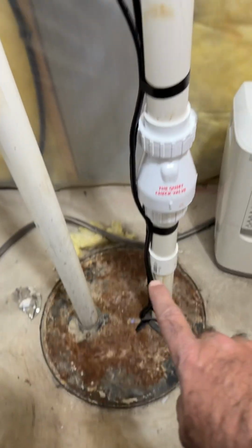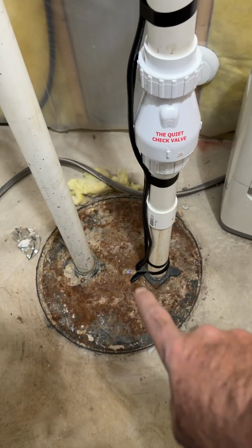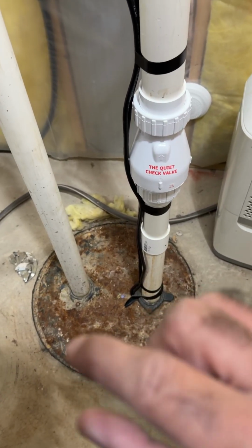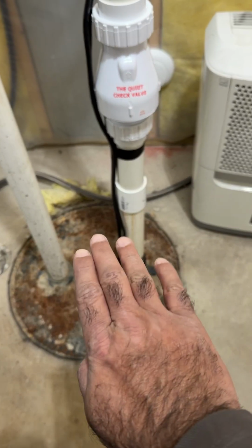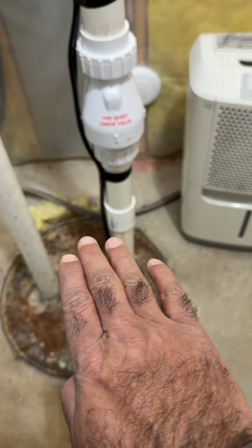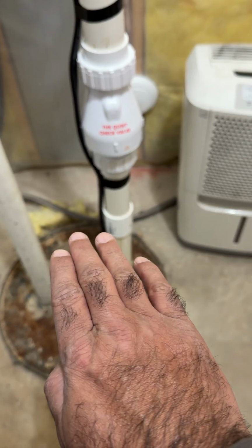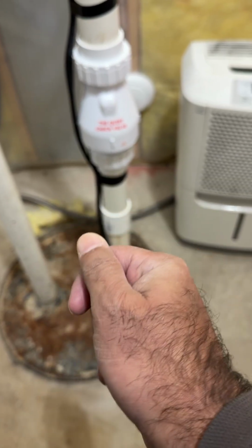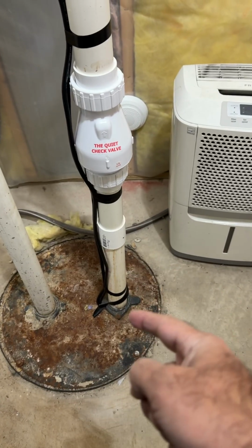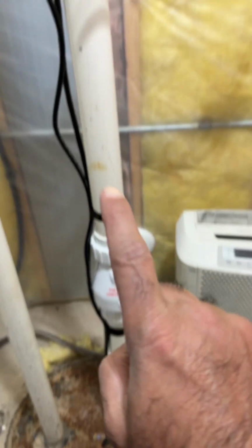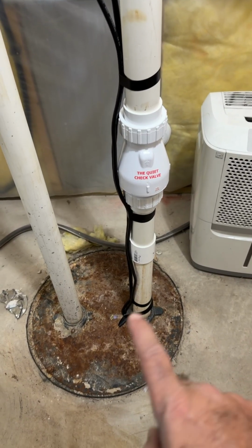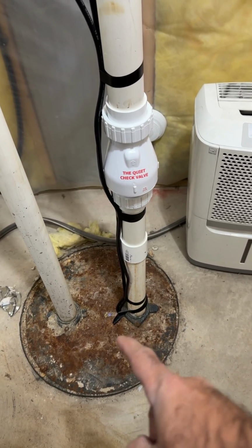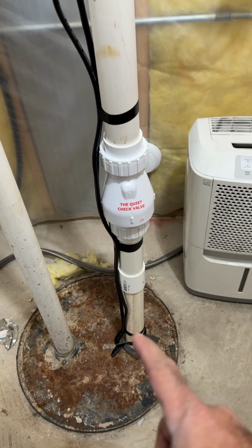So what happens? First thing you have to see is whether your pump is actually working or whether there's a problem with the switch mechanism. Think about it this way. Inside the ejector pump, the sewage level will begin to rise. When it rises to a certain level, it hits a switch. The switch turns the motor on, and the pump motor shoots everything up into the main sewage line. So if the switch doesn't turn on, then the pump may not turn on. And sometimes you have to figure out why that is.